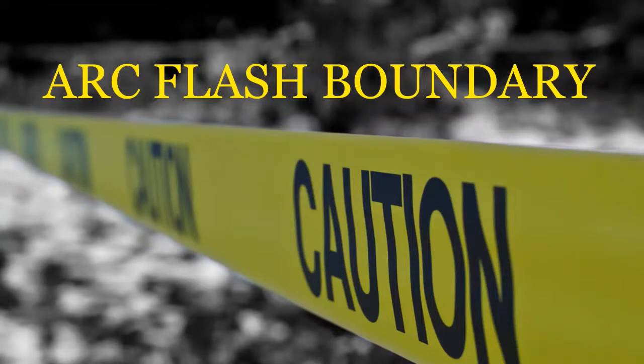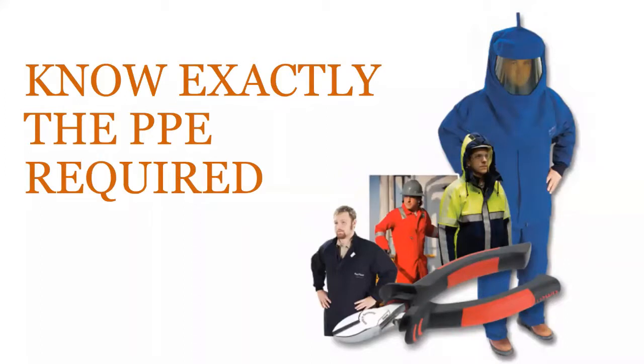So you probably want to keep them even a little bit further away from that boundary, but that gives you a sense of how far away. So maybe, for example, you're working on an MCC bucket and you know that the incident energy is 8.3 calories per centimeter squared. That's telling you what PPE you need to have on for protection. And the boundary might say 10 feet. So you know that everybody else who's not wearing protection needs to be at least 10 feet away. And so those are some of the details. Fundamentally, once you have the arc flash study completed, then you know exactly what PPE you need for the jobs.